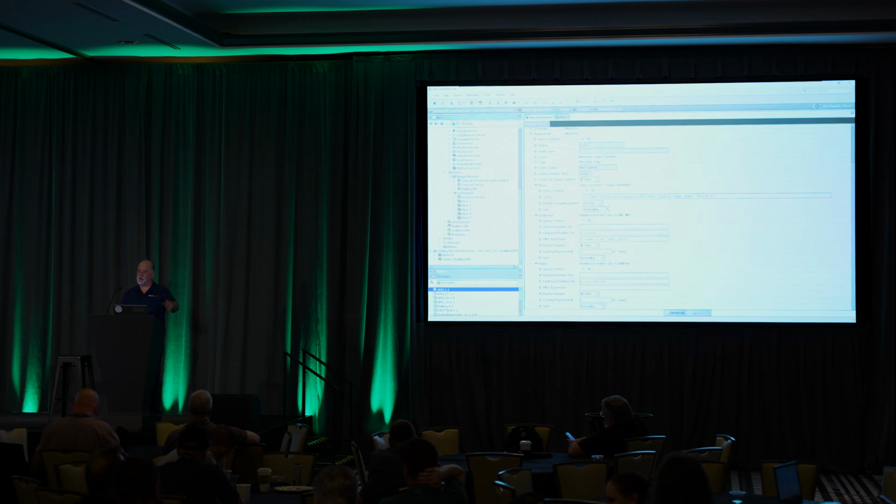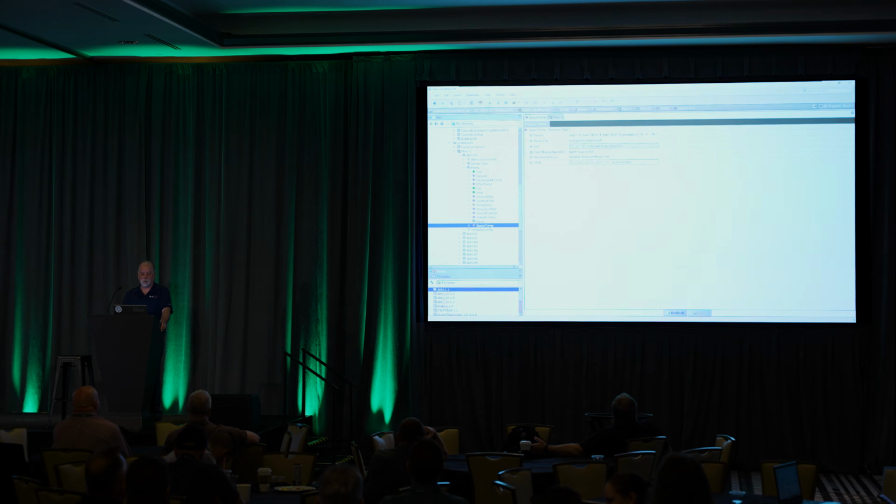How many of you have set up history groupings before? Right? Okay. Pain in the butt, right? I shouldn't say that, but hey, things can be a little bit difficult. When you want to set up history groupings, you either use that metadata browser that historically has been slow, or you use the batch editor, and you go to your control points, to your history extensions, and you add string slots to your history config.